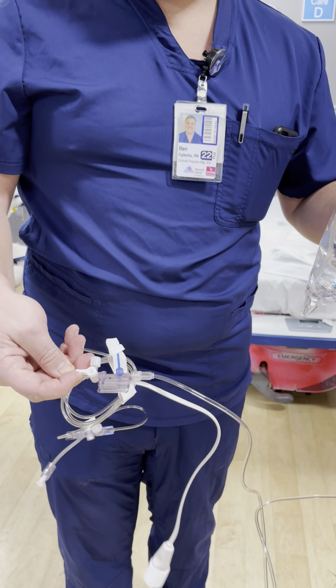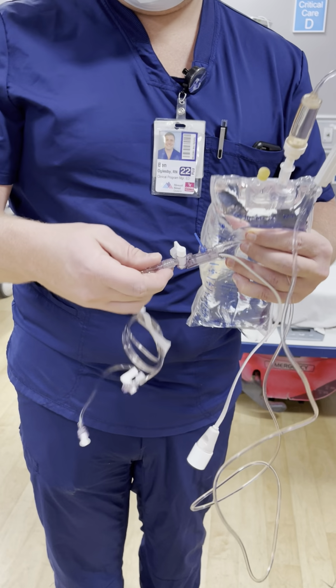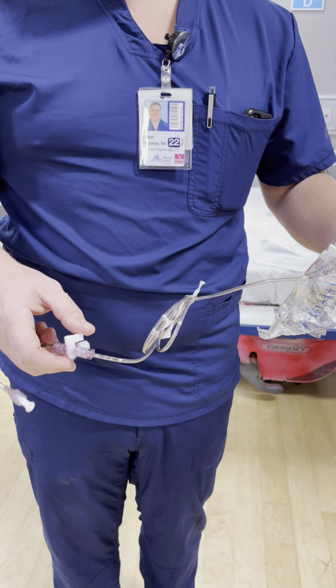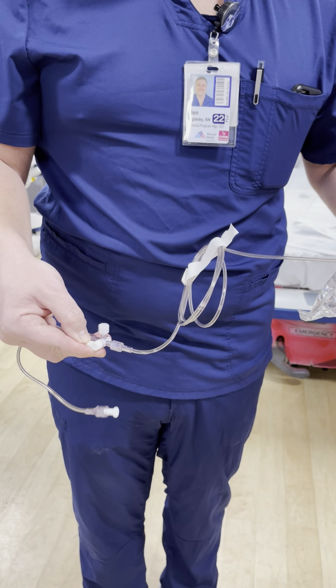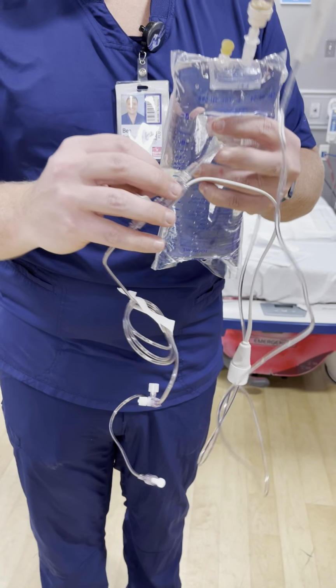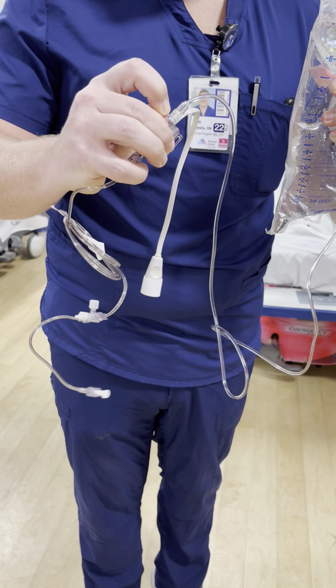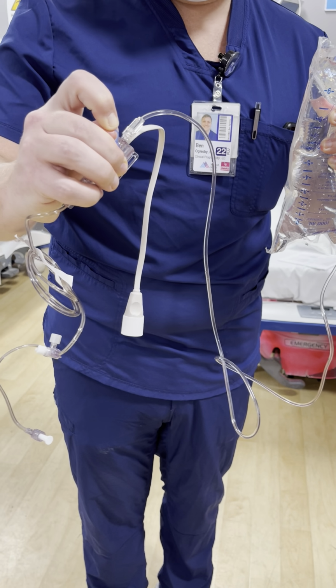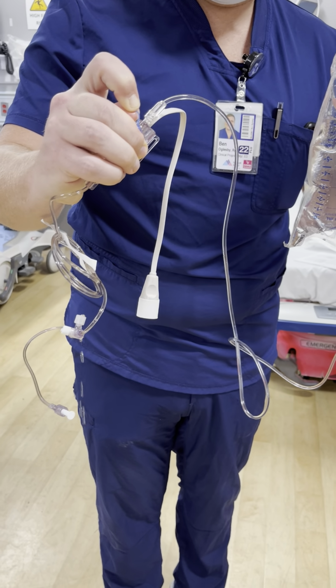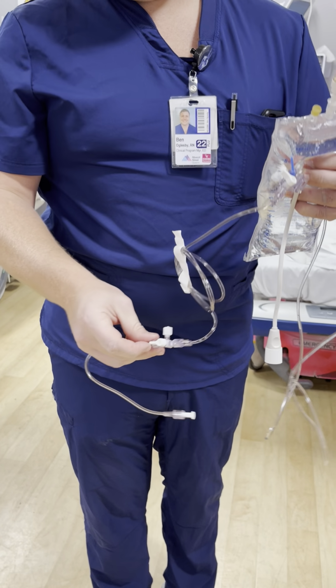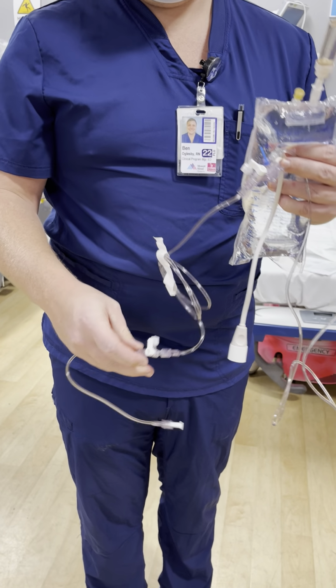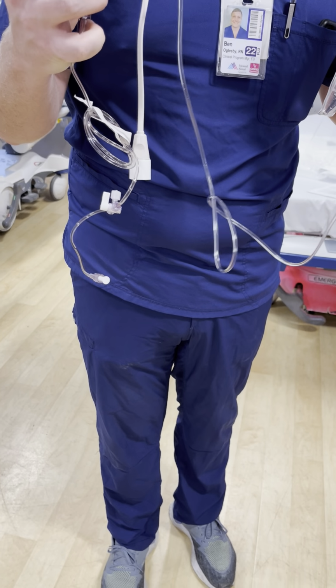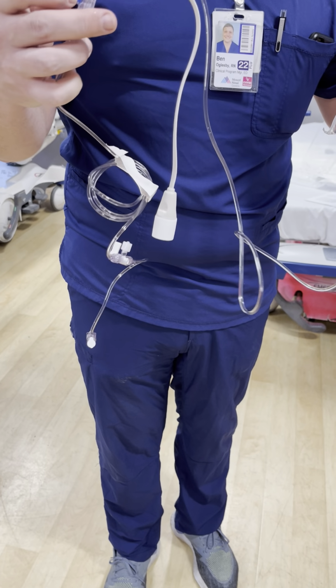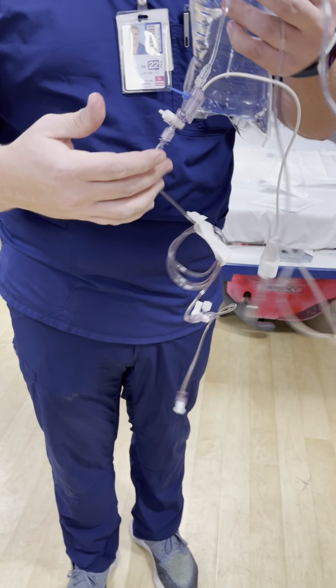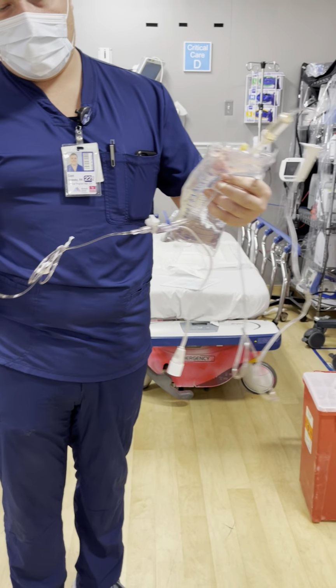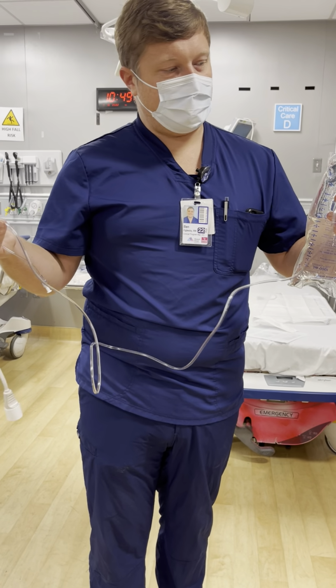And then you're going to turn the stopcock back to be open, and then you're going to move down to the next available stopcock closer to the patient. Once again, turn it off to the patient. So when you do that, you're going to come back to the blue tab, and you're going to pull it again and continue priming your line until fluid comes out at that stopcock. And you can stop. And one more time, we're going to flip the stopcock to the open position and then prime all the way to the patient side. Once you get to this point, you're going to visually inspect your entire length of your tubing. Make sure that there are no air bubbles, and that way you know your entire system is completely primed.